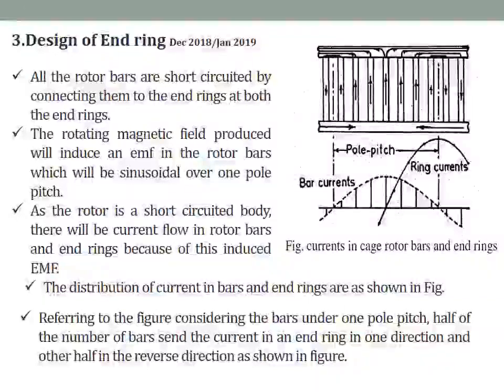Now to consider the end ring design. We know that all the rotor bars are short circuited by connecting them to the end rings at both the ends. Now you can see here, this is the end ring and this is the end ring, and these are the bars. The rotating magnetic field produced will induce an EMF in the rotor bars, which will be sinusoidal over one pole pitch.